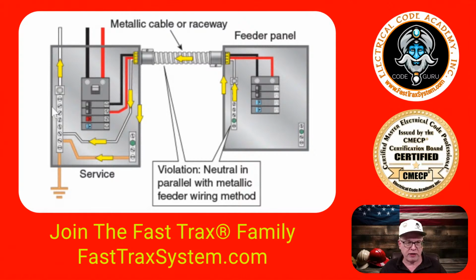You could have just put a green screw in here and called it a day, but there's a lot of reasons why we separate these in our illustrations in our grounding and bonding course. It's because we want to take the opportunity at certain times to size this main bonding jumper if it's of the wire type. So we break it out so that we can teach you a lesson in sizing.